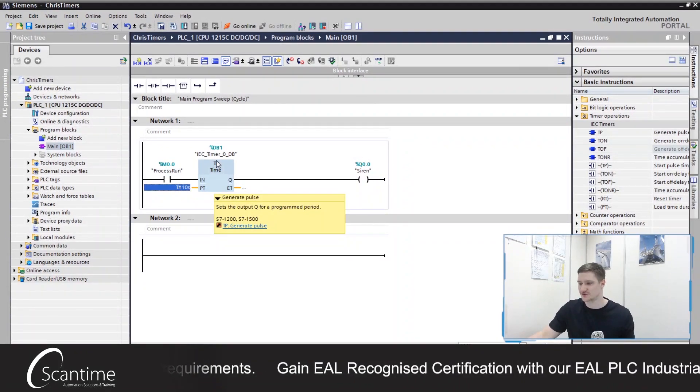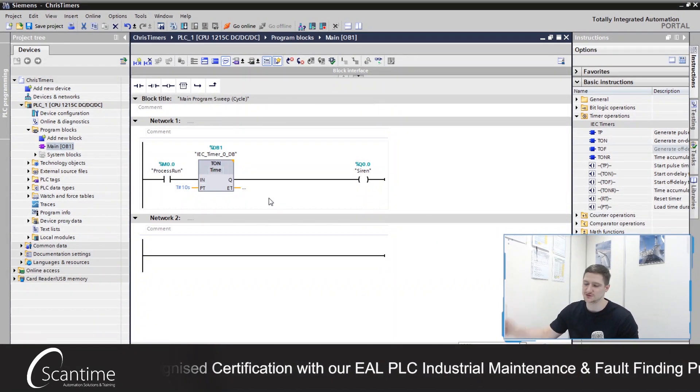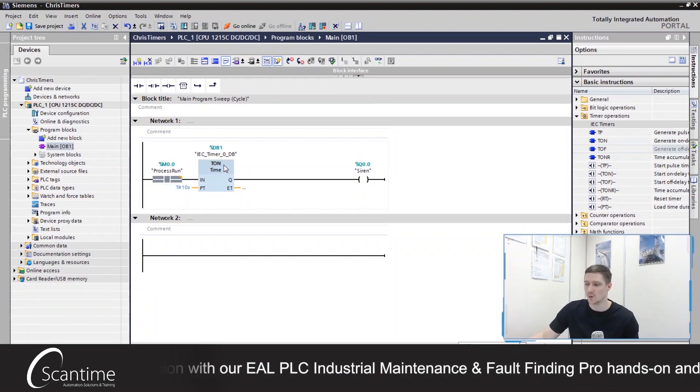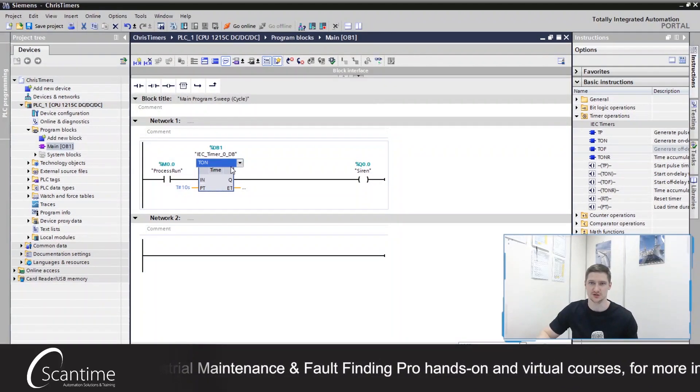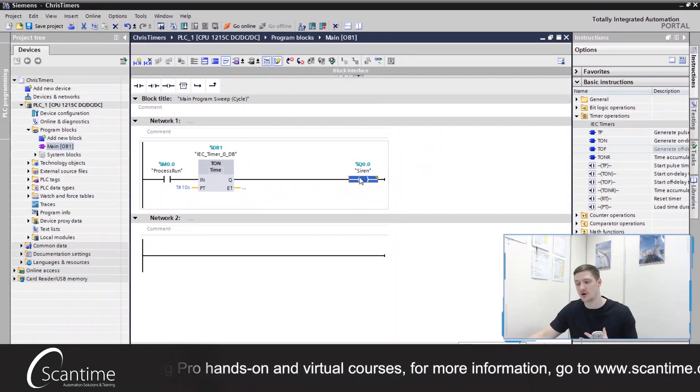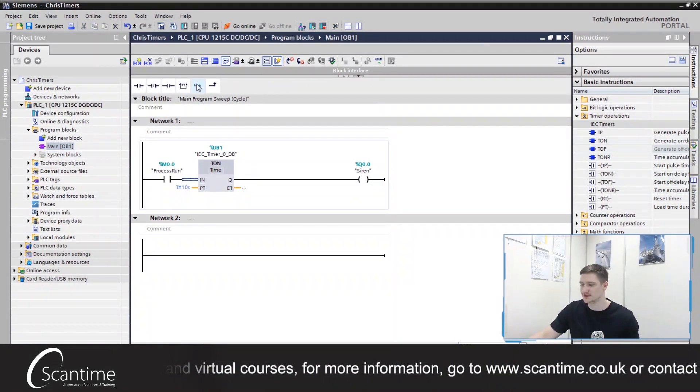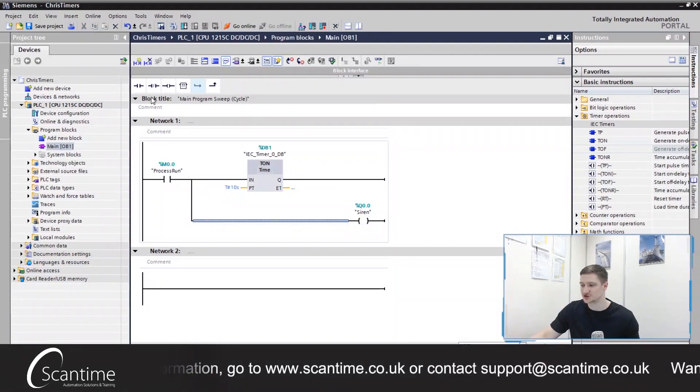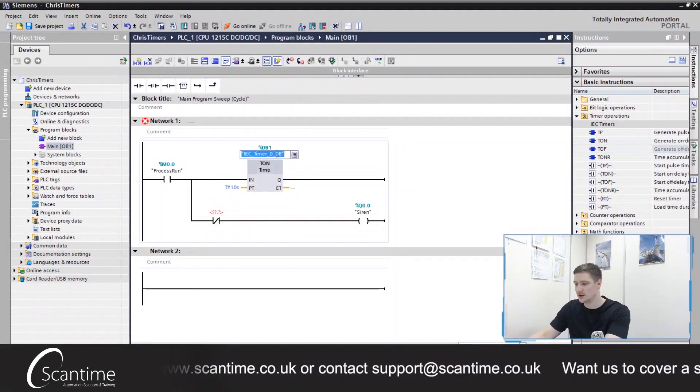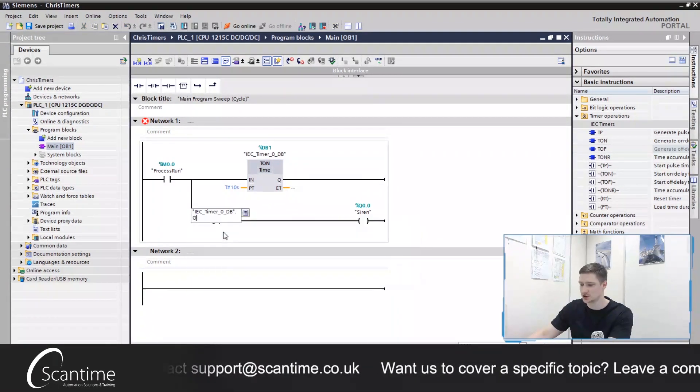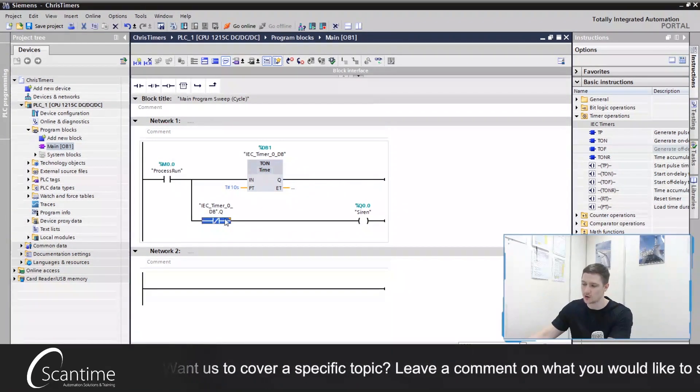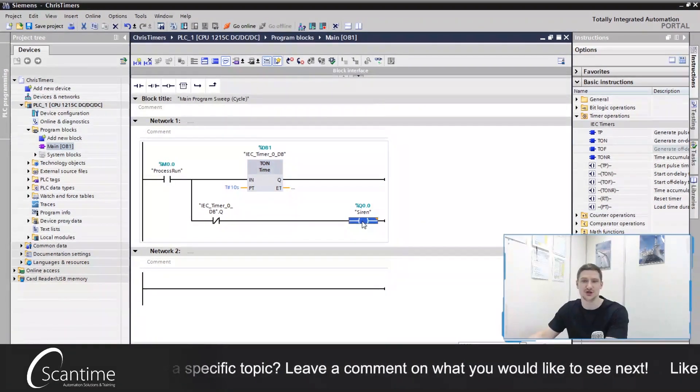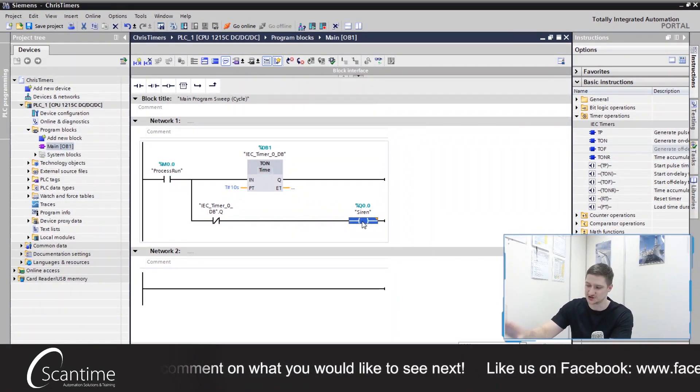To create that using an on delay timer we just use standard bit logic. So here for example let's change this to a TON. When the process turns on it's going to wait and then turn on the output. So I'm going to simply branch down, move the siren below and place normally closed contact from the data block of the timer dot Q. When that turns on after 10 seconds it'll then open and turn off our siren.